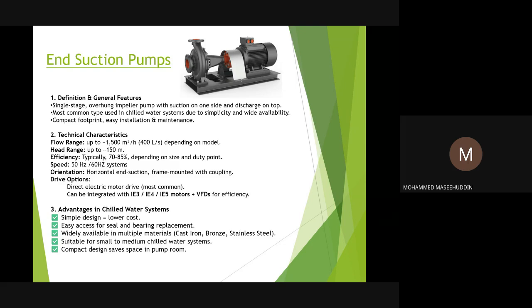What are the advantages of this in chill water systems for the end suction pumps? Because it is simpler in design, it obviously lowers the cost of the pump itself, and it is easily accessible for seal and bearing replacement, as I told you, since it is BPO type, back pull-out type. The maintenance of the pump is very easy, and it's available in multiple materials of construction. MOCs are like cast iron, bronze, stainless steel, etc.